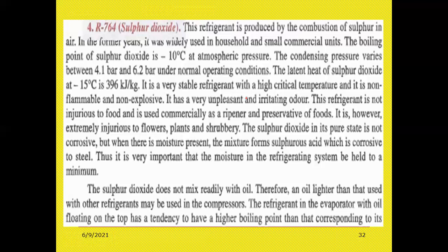However, it is extremely injurious to flowers, plants, and shrubbery. The sulfur dioxide in its pure state is not corrosive. Pure state alone, it is not corrosive. But when there is moisture present, it turns to sulphurous acid, which is corrosive in nature. Thus, it is very important that the moisture in the refrigerating system be held to a minimum.